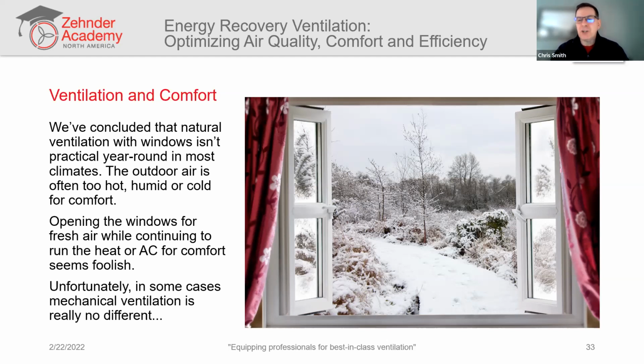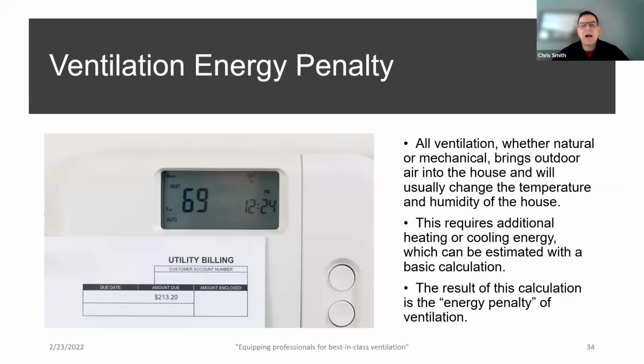We probably wouldn't do that. Common sense would say you don't leave the windows open all winter long. But unfortunately, in some cases, mechanical ventilation is really no different, because when we're using supply and exhaust fans to drive our ventilation, that infiltration and exfiltration is the same volume of air coming into the building. And because we're changing outdoor air with indoor air, we're changing the temperature of the air in the building. The set point on our thermostat will be triggered, and our heating or cooling systems will be running more to deal with that mechanical ventilation. So this additional heating or cooling energy can be estimated with a pretty basic calculation, and the result of that calculation is what you can call the energy penalty of ventilation.